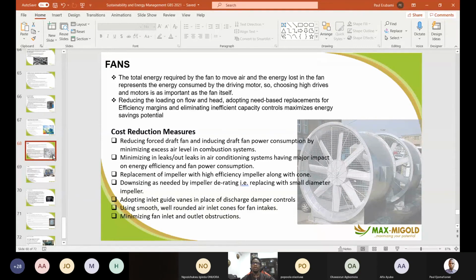And then for fans, they help to move air around. You could have a pressurized stairwell for evacuation. You could have ventilation systems that are operated by fans. You reduce forced draft fan and induced draft fan power consumption by minimizing excess air level in combustion systems. Minimize in-leaks and out-leaks in air conditioning systems, having major impact on energy efficiency and fan power consumption. Replace impellers with high efficiency impellers, where the impellers are no longer efficient.